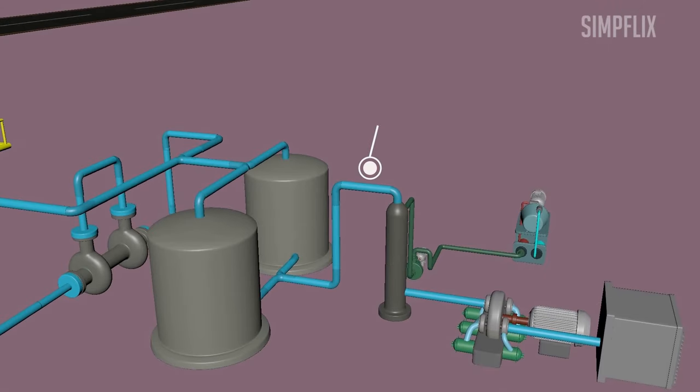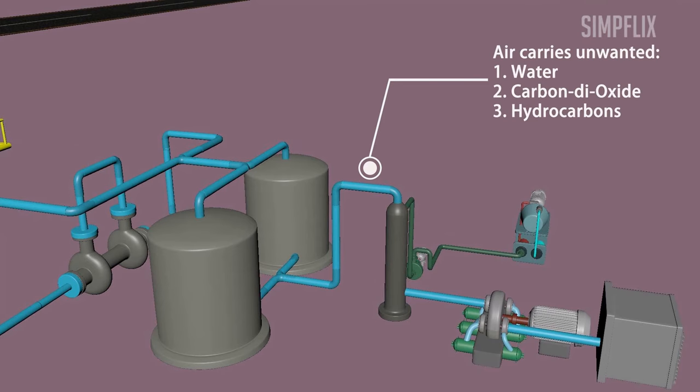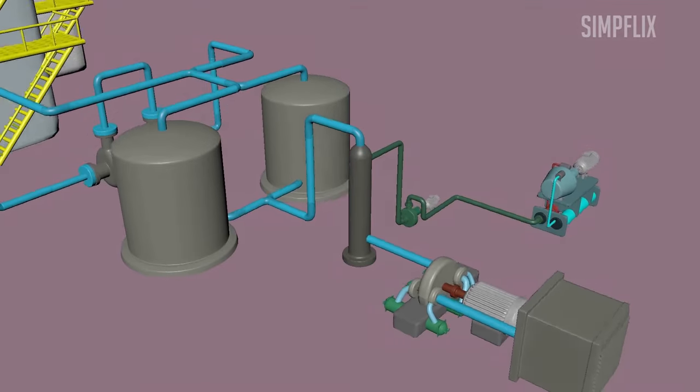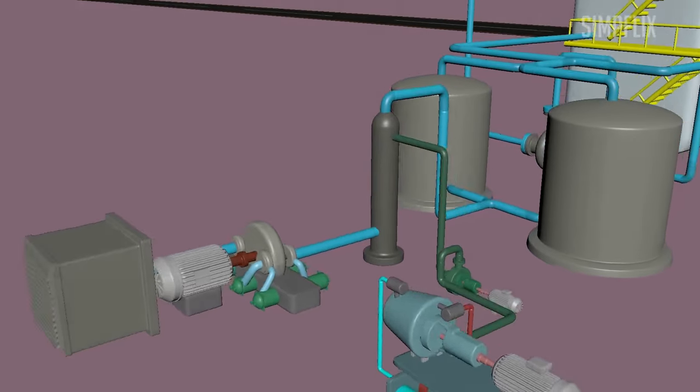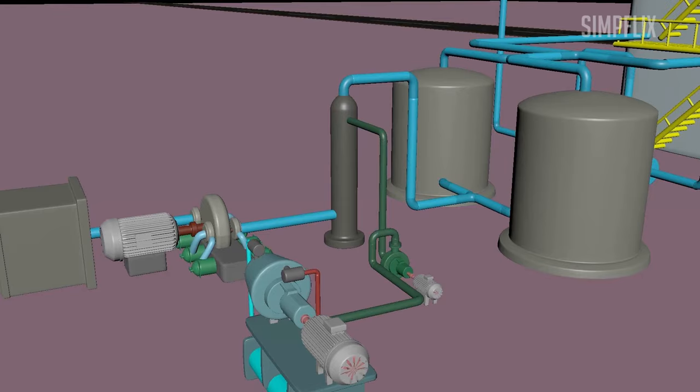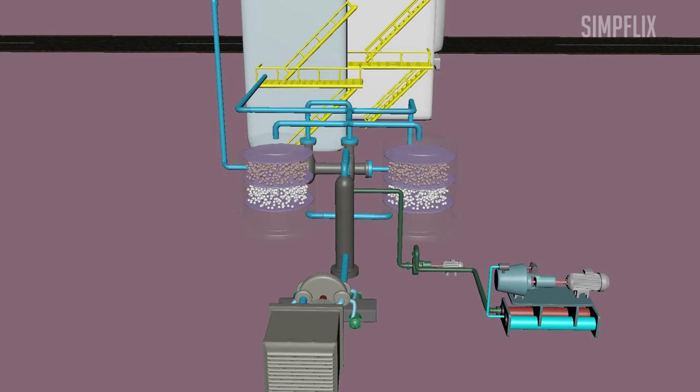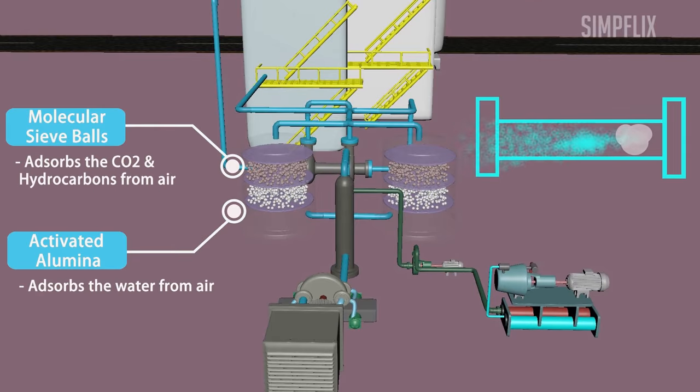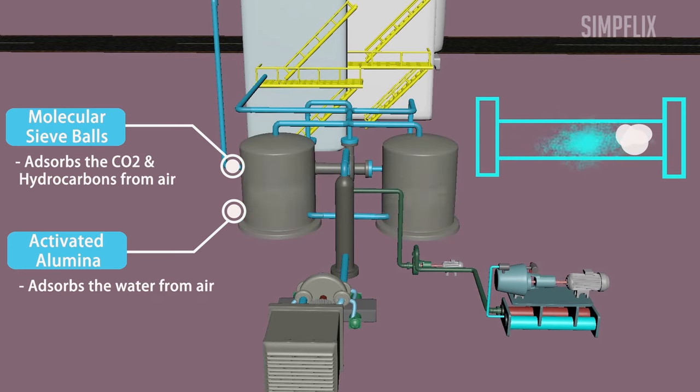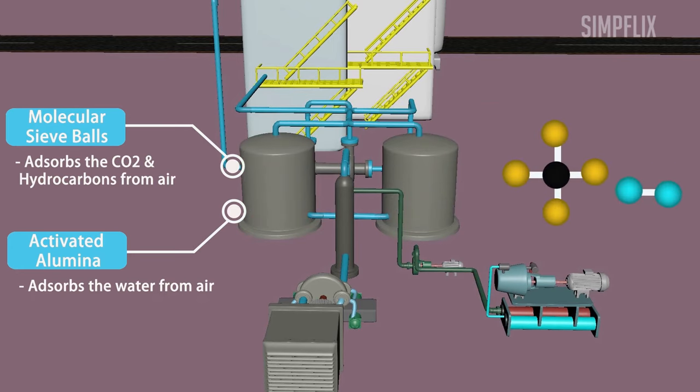So at this stage, high pressure, low temperature air is having impurities like water, carbon dioxide and hydrocarbons, which are not required. Water, hydrocarbons and carbon dioxide are removed in the purification units using molecular sieves and activated alumina. If water and carbon dioxide are not removed, then they will form ice in the lines and result in blockage of the air path. If hydrocarbons are not removed, then it will result in explosion if it accumulates in liquid oxygen.